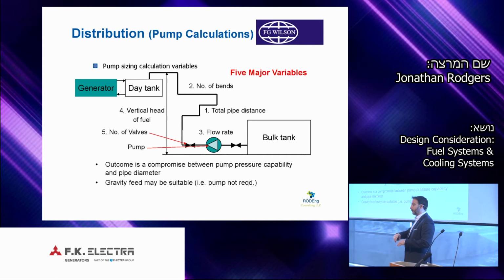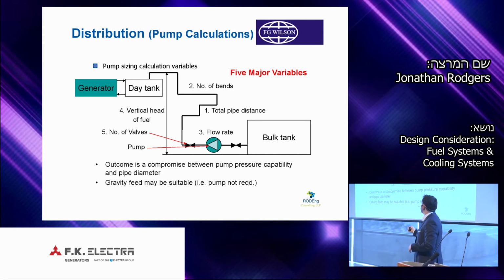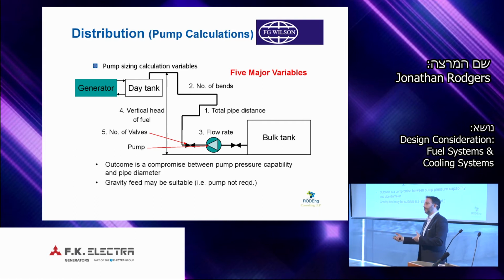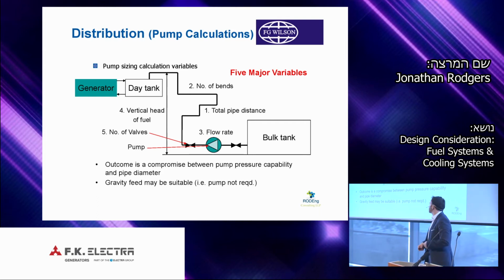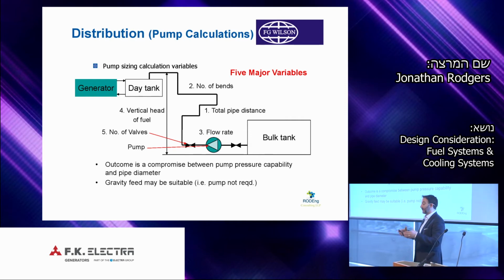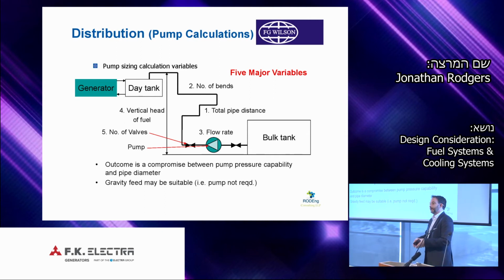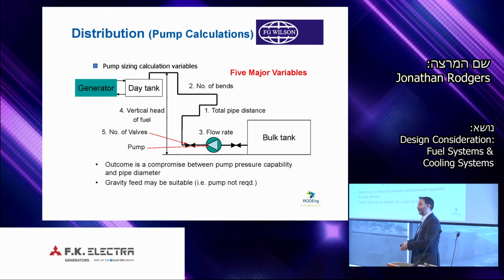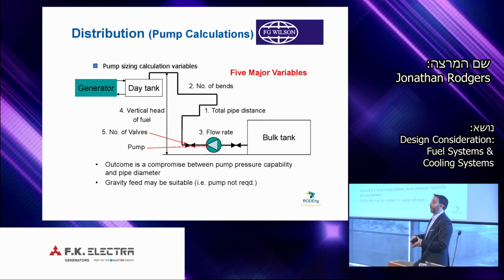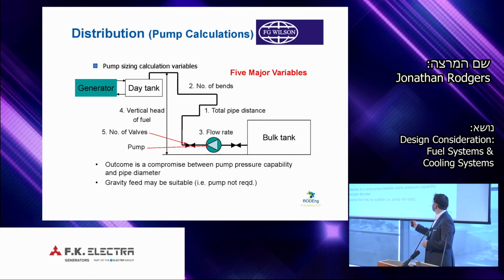Then we look at the vertical head that we have to pump to overcome, and then the number of valves, because each valve will have a resistance that we need to consider in our pressure calculation. And what we have in the calculation, we have a compromise between the size of the pump and the size of the pipe. And we calculate, based on pressure, the most practical, usable size of pump for the minimum pipe diameter that we can.